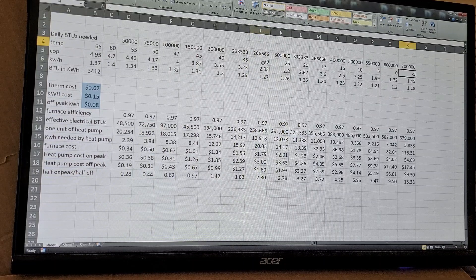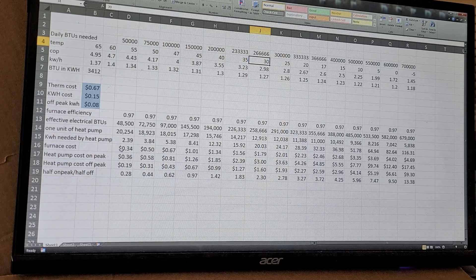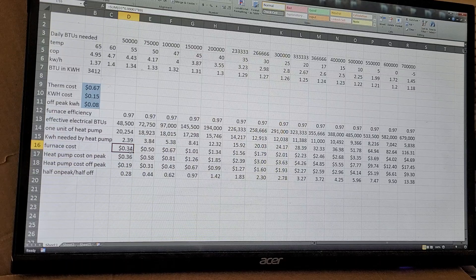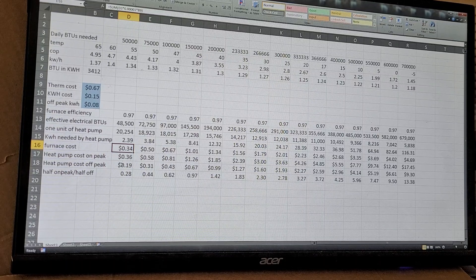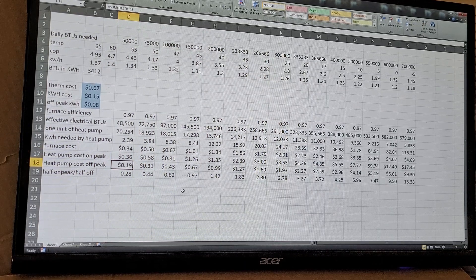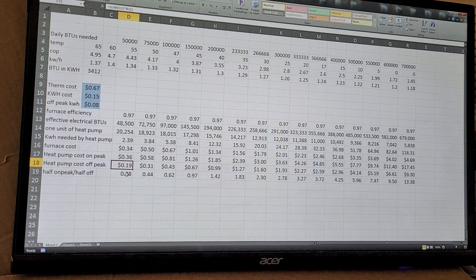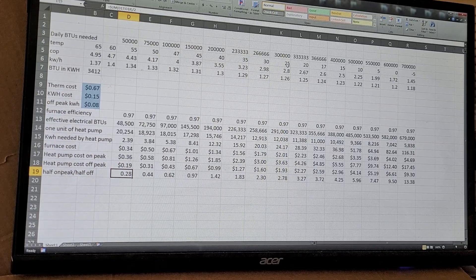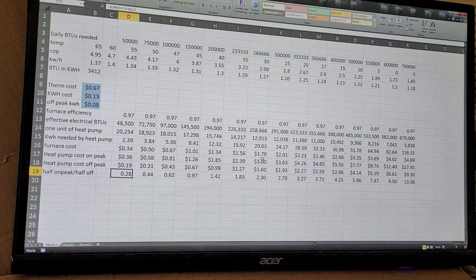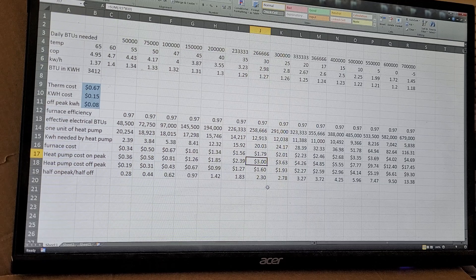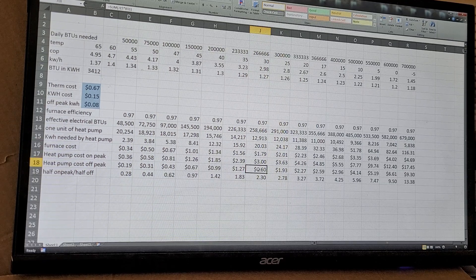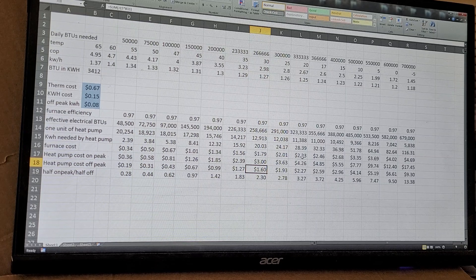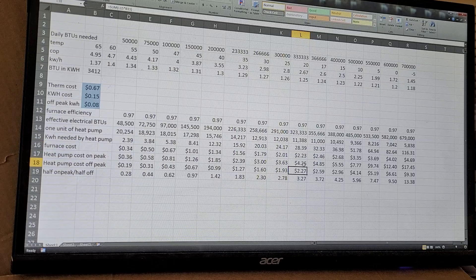Now down here, at my current rates, it costs me 34 cents to run the furnace to keep it warm for a day. On-peak it would cost 36 cents electric, and off-peak would cost 19 cents electric. If you kind of do a half on, half off, I just took the mid number from that. So when it's 30 degrees outside here, it's going to cost a dollar seventy-nine to run the furnace, three dollars on-peak with the heat pump, and two dollars sixty off-peak. So it's still cheaper at that point.